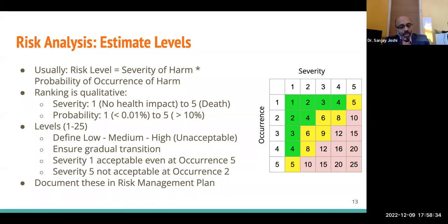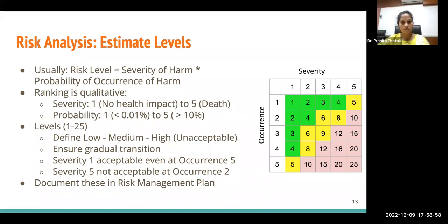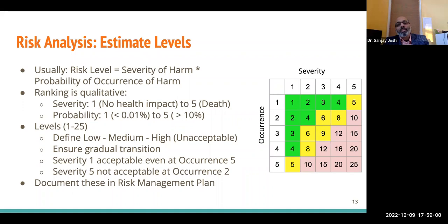One thing to clarify there, Pranita, is that the governments typically do not say that you have to have the certification to the standards. So it's not a requirement. It's recommended. It's not a requirement. So technically speaking, somebody could go to the government and get their device or product approved without going through ISO or IEC certification. That's totally possible. However, the kind of documentation, the kind of paperwork you need to submit is probably compliant with the ISO standard anyway.